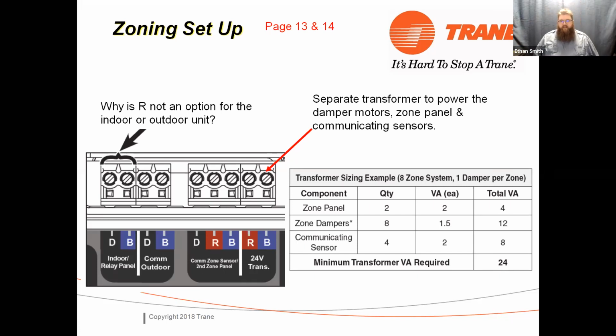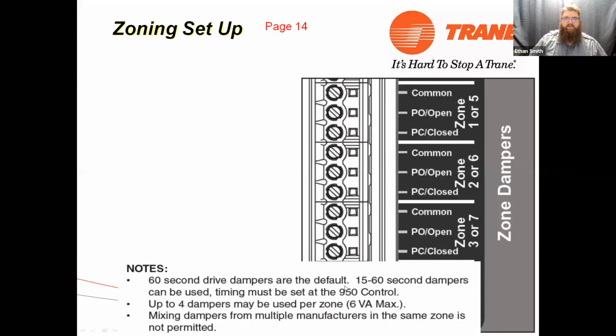So if you just go and pick up a second furnace transformer, that'll generally do everything you need it to. Obviously, if you're using somebody else's dampers, you want to check out the VA rating on those. I know that the Carrier dampers, I think, are 2.25 VA, and some of the Honeywell dampers are even higher than that. So make sure that you're meeting your power rating when you supply that transformer.